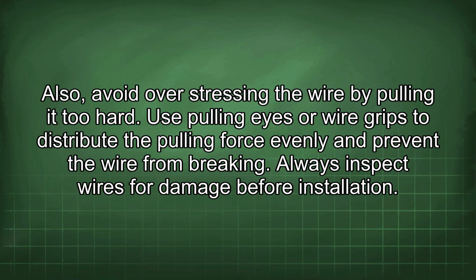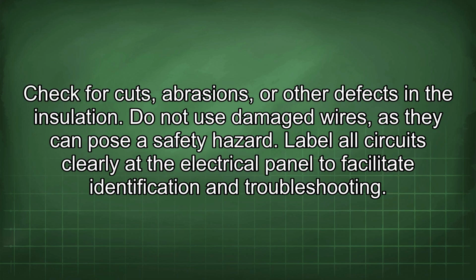Use pulling eyes or wire grips to distribute the pulling force evenly and prevent the wire from breaking. Always inspect wires for damage before installation. Check for cuts, abrasions, or other defects in the insulation. Do not use damaged wires, as they can pose a safety hazard.